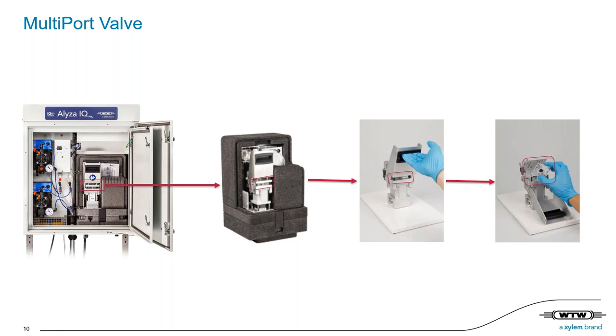Designed as the main spare part of the new analyzer with a long lifetime, it will need to be replaced only once per year. In addition, as this is a spare part, this guarantees always reliable and extremely accurate measurement values without wear-out effects. And as I always mention, the exchange is as simple as a coffee pad machine. So just open the holder, remove the old one, insert a new one, close the holder, and just start the measurement.